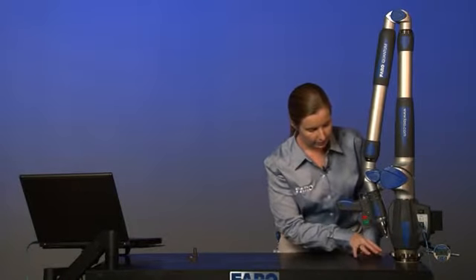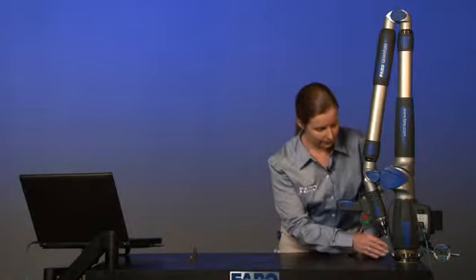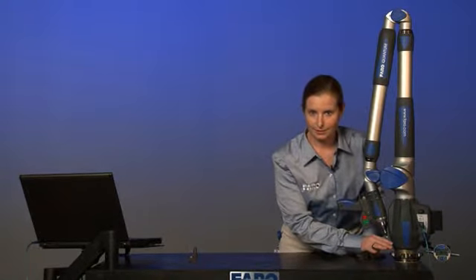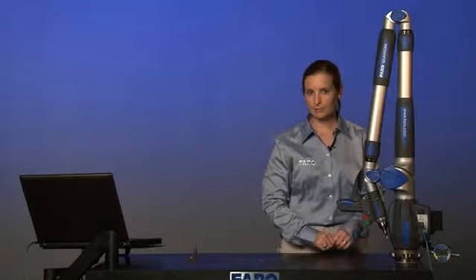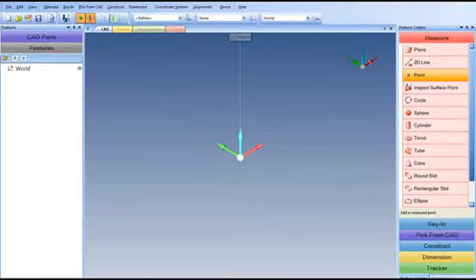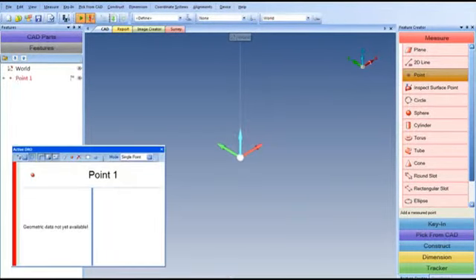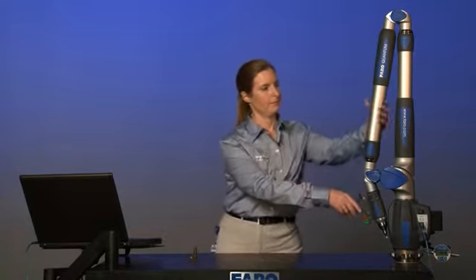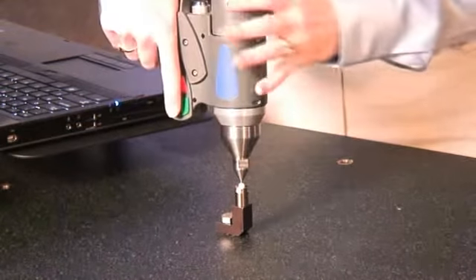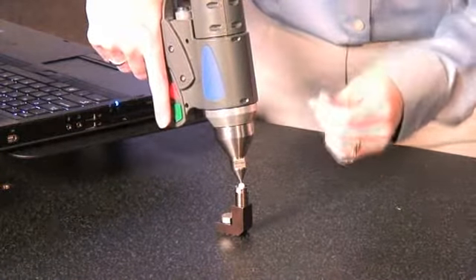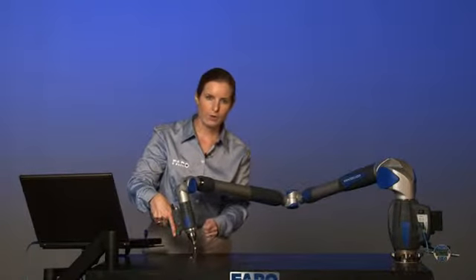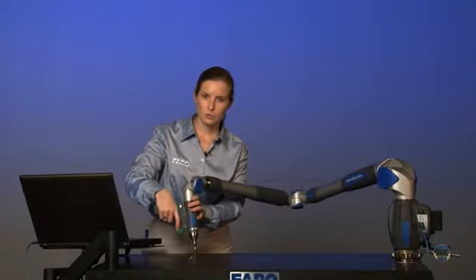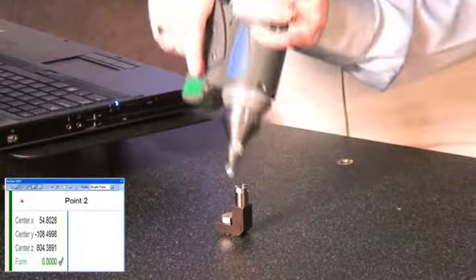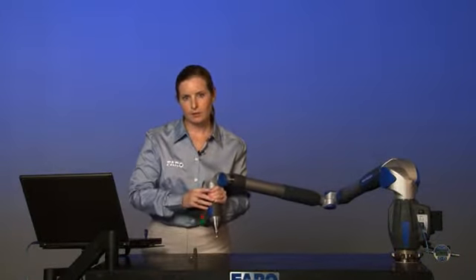With our setup here, we're fixed right to the granite surface. We have a dial indicator to verify that the arm isn't moving. You don't always need to have a dial indicator to verify that the arm isn't moving. There are other ways to check the stability of your mounting environment, and one is to use the FARO Arm itself. If we start in the software, go to the Measure menu and select Point. With the tip of the probe rested securely within either the calibration cone or within a hole smaller than the diameter of the probe where it can pivot, you want to take a point, record that point, and then we can bring up a digital readout to this point to verify that the arm isn't moving.